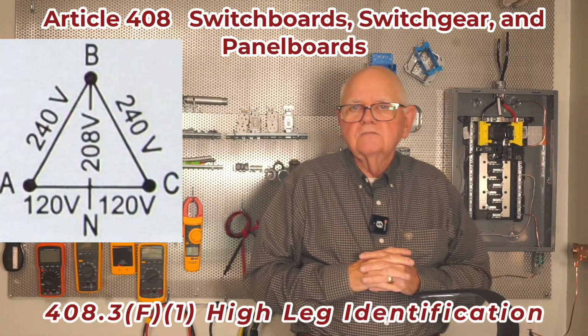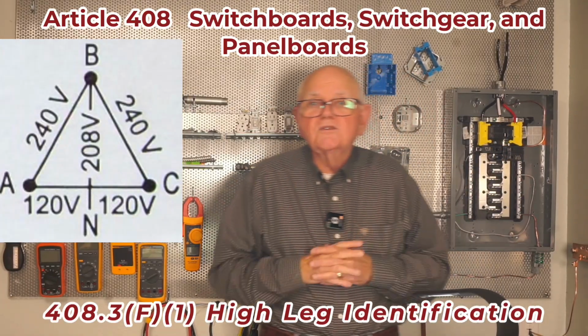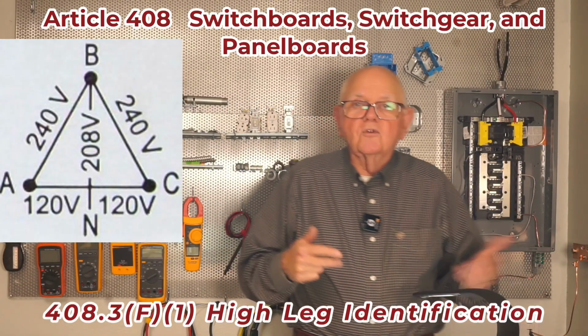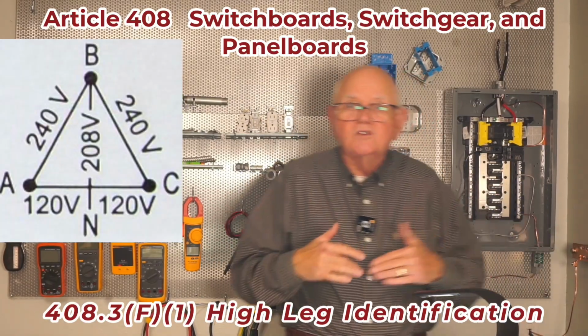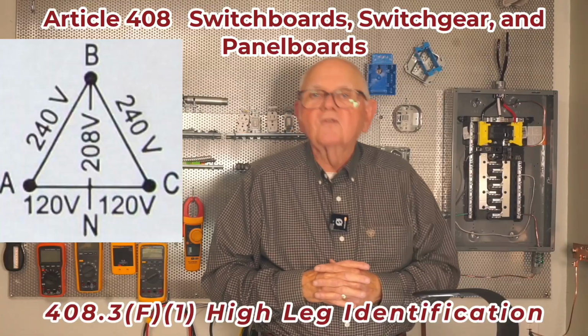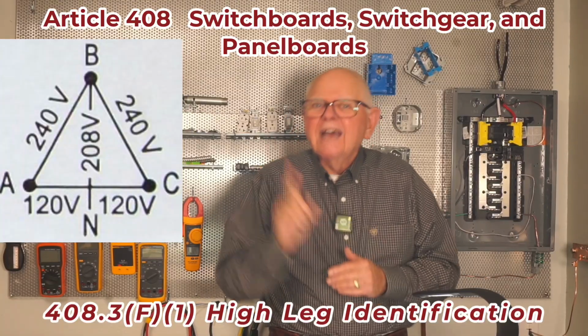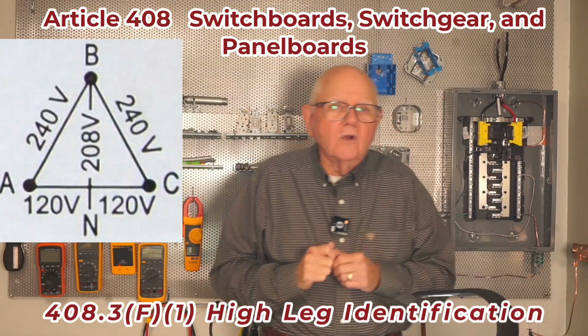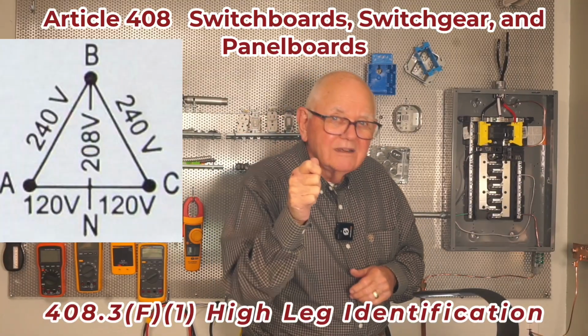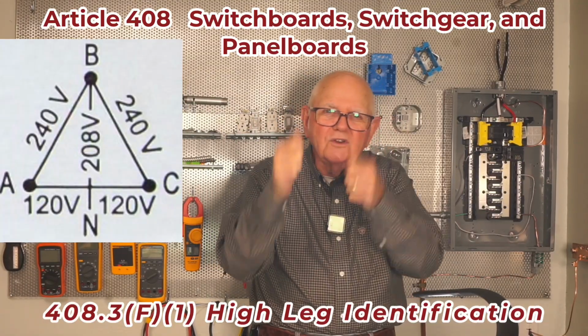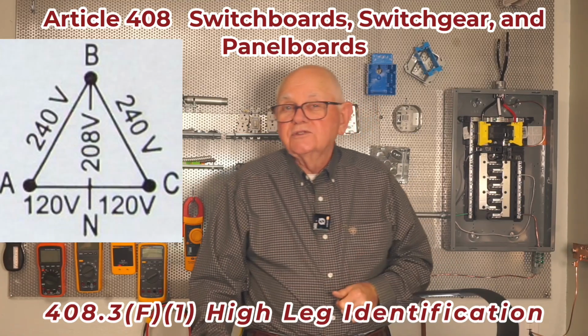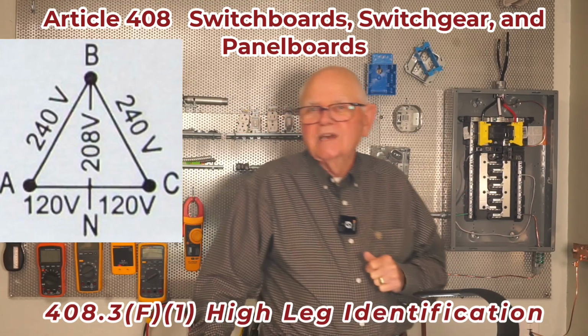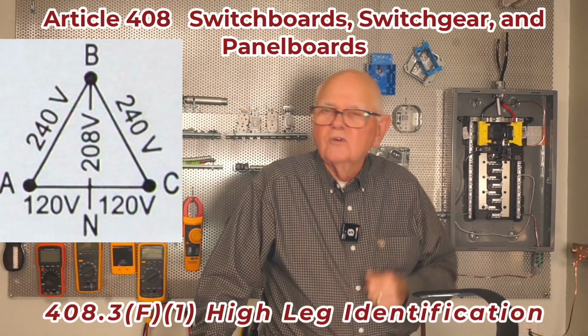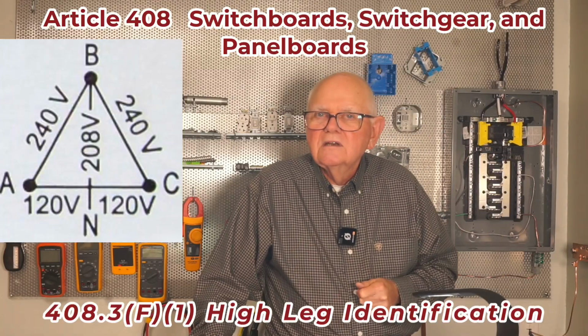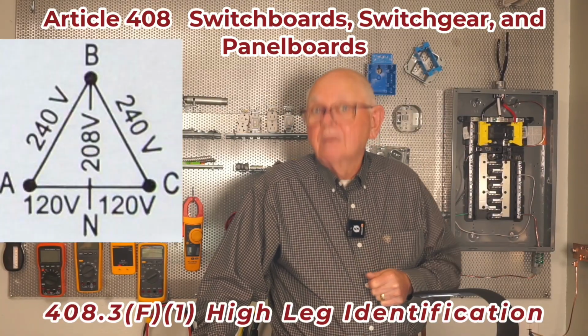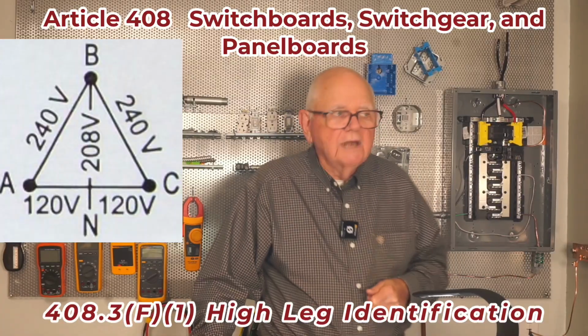I would take that neutral and run that into my panel board. So what do I have? Looking at my delta transformer, reading from either the black or the red, from either the bottom left or bottom right phase to the neutral, I get 120 volts. That's great. But if by accident I go to the top of that delta connected transformer and connect that ungrounded conductor with the neutral, I've got 208 volts. Surprise if I'm wiring up some receptacles, isn't it? Or a 120 volt motor, lighting, whatever it is. I've just probably burned up some equipment. I made the smoke come out of it, right? And that's not good.